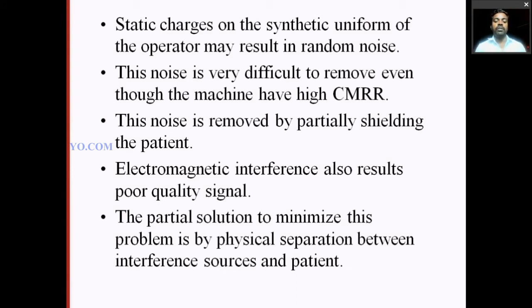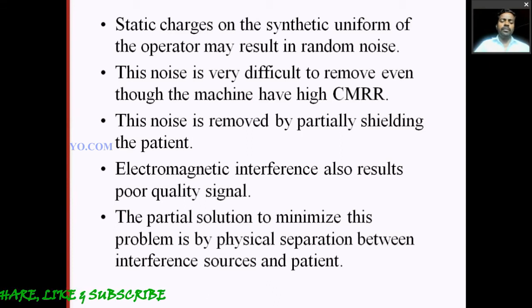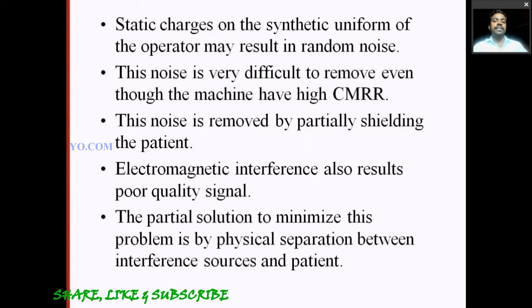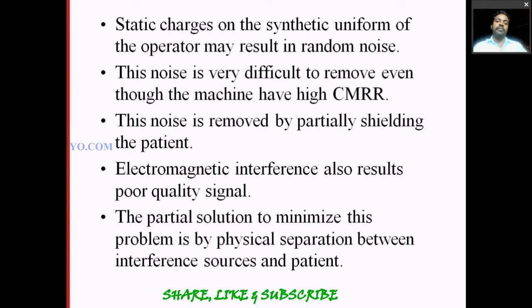Electromagnetic interference also results in poor quality signals. Electromagnetic interference comes from devices like fans and motors, where an electromagnetic field is generated by electric charge, current, voltage, and the rotating magnet. A fan or motor executes the electromagnetic concept, creating interference that affects the signal. The partial solution to minimize this problem is physical separation between the interference source and the patient — increasing distance reduces interference.